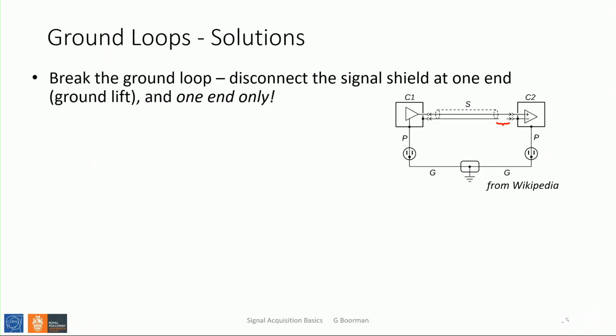You've got to, in essence, break the loop - break the ground loop. There's lots of ways of doing it. So for instance, this is exactly the same diagram but without the magnetic fields and current. You can see on the BNC cable, assuming it's a standard shielded cable, it's actually got a break at one end, and that break breaks the loop. As soon as you don't have the loop, you can't induce a current in it.